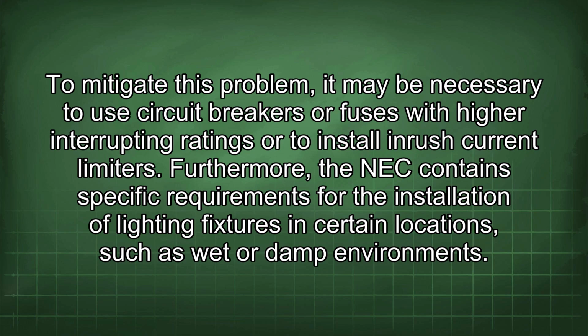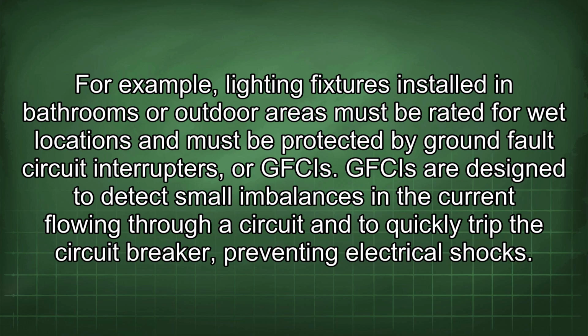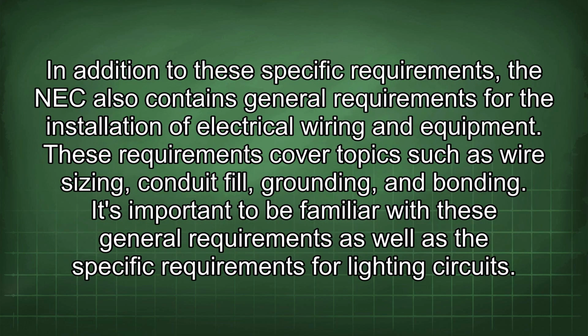Furthermore, the NEC contains specific requirements for the installation of lighting fixtures in certain locations, such as wet or damp environments. For example, lighting fixtures installed in bathrooms or outdoor areas must be rated for wet locations and must be protected by ground fault circuit interrupters, or GFCIs. GFCIs are designed to detect small imbalances in the current flowing through a circuit and to quickly trip the circuit breaker, preventing electrical shocks.